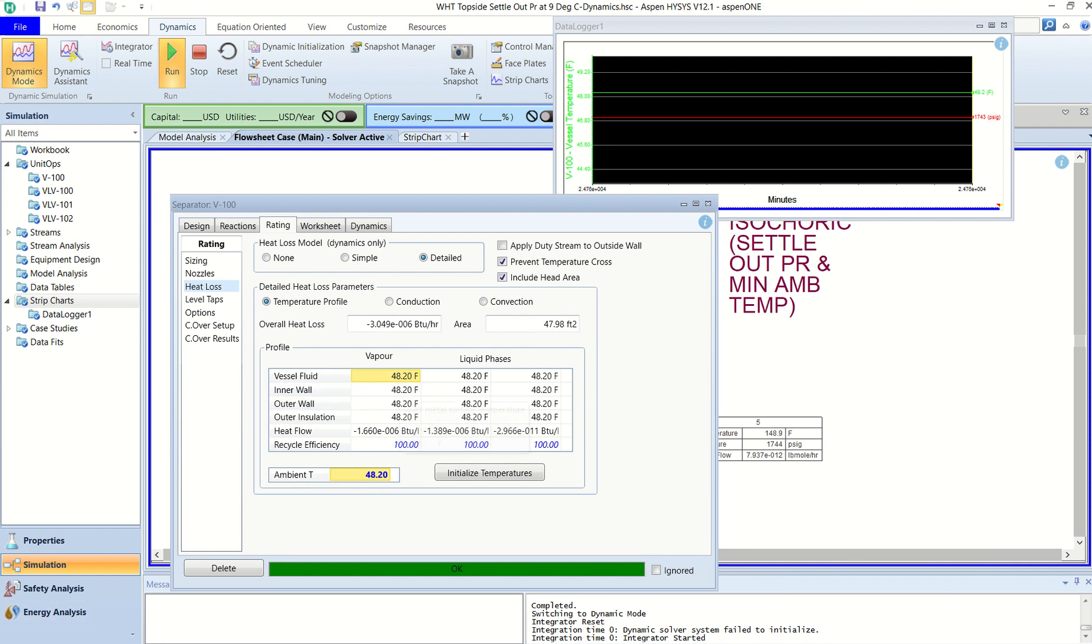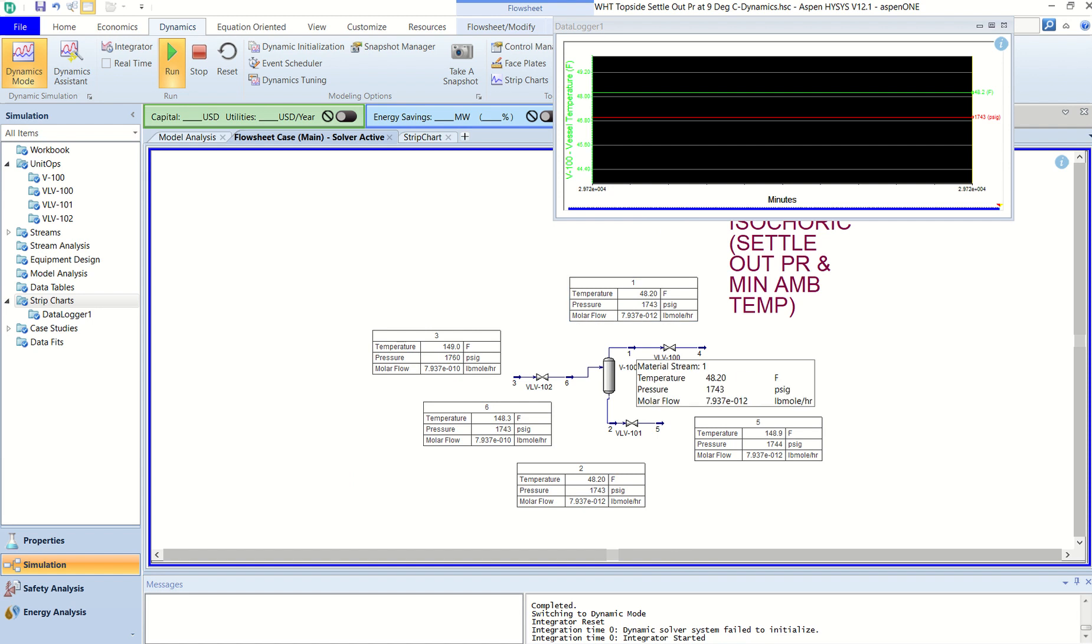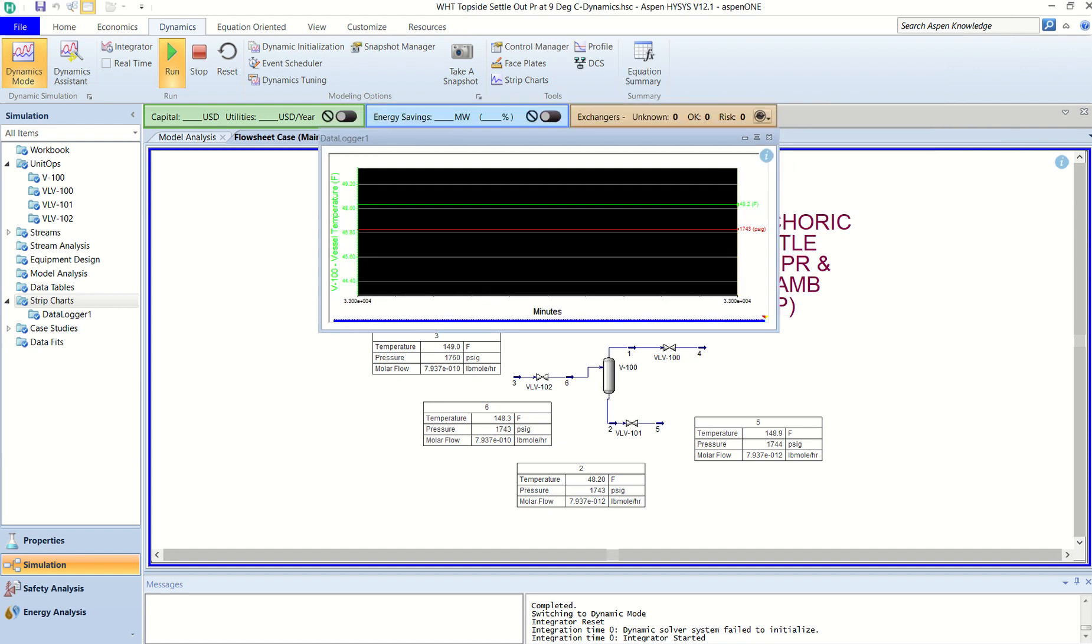Vessel fluid is 48°F, inner outer wall 48°F, everything is in equilibrium with the ambient. And what is the final pressure that you are talking about here is 1743 psig. 1743 psig is the final pressure on which it is going down. Still your integrator is running and you can see this pressure and temperature is still constant with almost no flow.